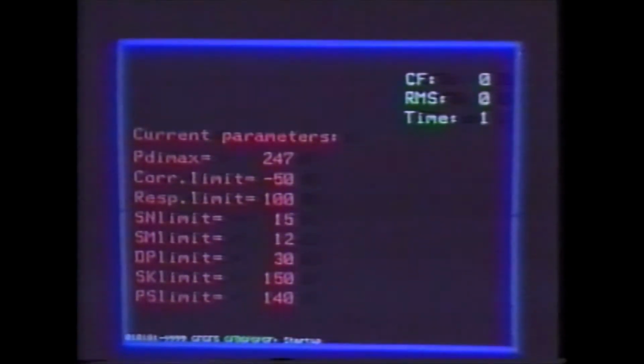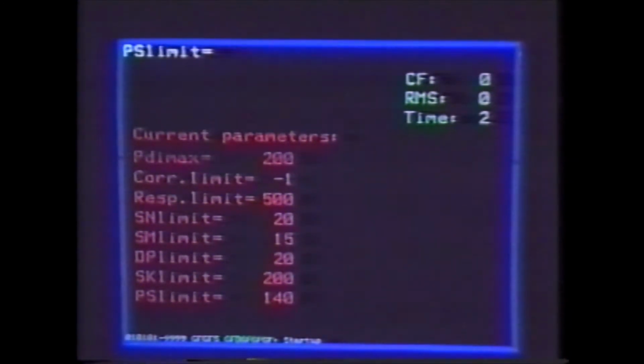Input keys are available for manual adjustment of the transdiaphragmatic pressure, correlation coefficient levels for detection of diaphragm position along the array, breath detection levels for determination of start and end of inspiration, and EMG signal quality indices, such as the signal-to-noise ratio, the signal-to-motion artifact ratio, the drop-in power ratio, the skewness index, and the power spectrum shape index. There are also various functions available to eliminate motion artifacts and to reduce noise.